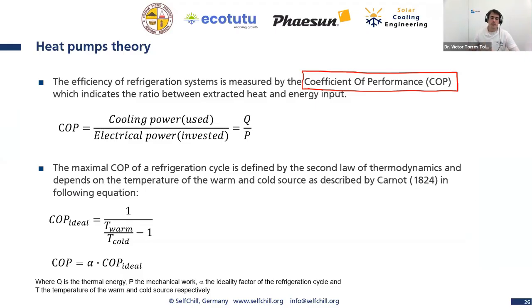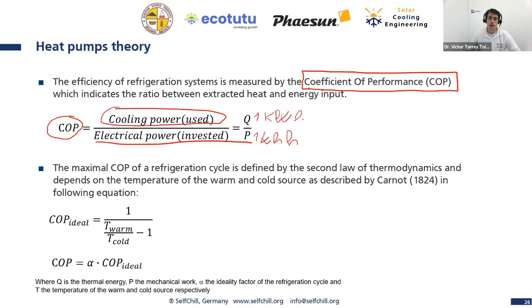We are pumping heat. That's why the coefficient of performance, COP, is the ratio between the cooling power, so this is the Q, the amount of cooling energy that we were able to pump from the outside into the inside, divided by the electrical power, the invested power. Okay, so let's say we have 1 kilowatt hour of electricity use, and we get 1 kilowatt hour of cooling energy. Then we'll have a COP of 1, right?